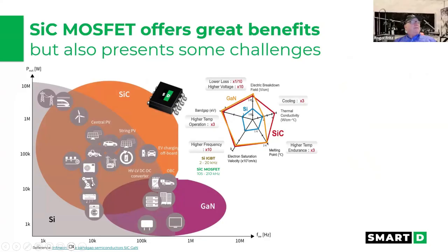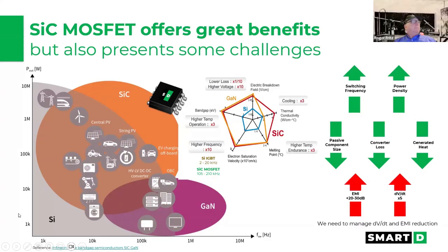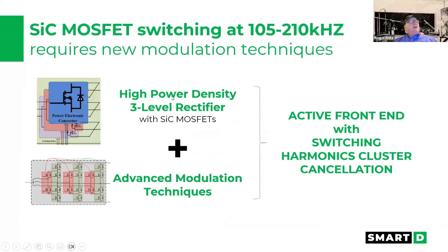They've been heavily involved in robotics, smaller applications, cars. They're working on some of it, wind, and very customized applications. But it's moving in to take over the VFD market over time. So the high density, 3 level rectifier with an active front end on it. We also don't need any dynamic braking. So any energy created back in the VFD from loading, let's say you have a pump jack, an escalator, elevator.